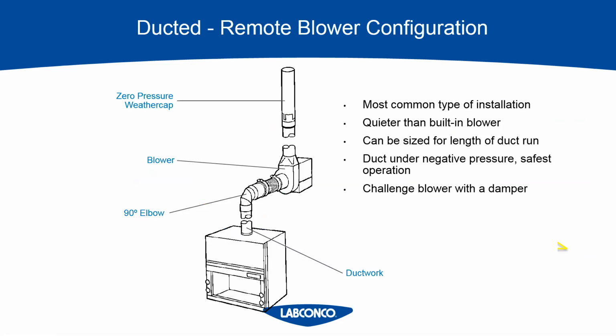These blowers have to be sized for the duct run, and this is the layout that you'll see for most installations. The air that's going through that fume hood is completely controlled by that exhaust fan. If you have a constant volume system, the air that is being exhausted through the hood is the same amount regardless of your sash position. So if you're exhausting 1,000 CFM with the sash open and then you close the sash, it's still going to exhaust 1,000 CFM. That's what a constant volume system is. That blower doesn't change RPM. If you have a variable volume system, the air being exhausted through the hood is different depending on the sash position. So you might exhaust 1,000 CFM with the sash open, and then that might drop to 200 or 300 CFM when the sash is closed.